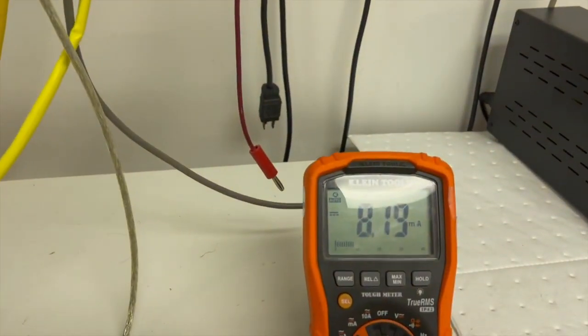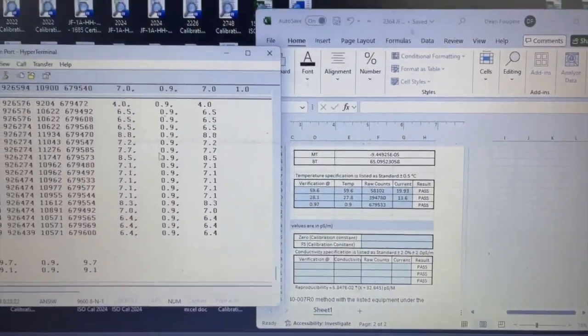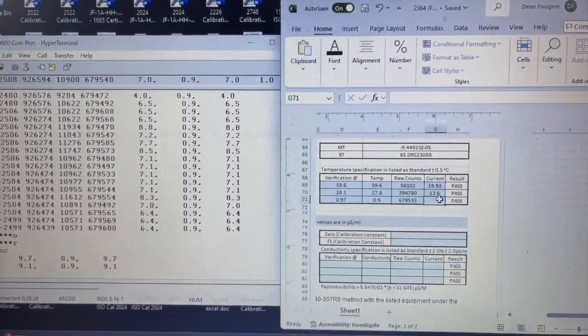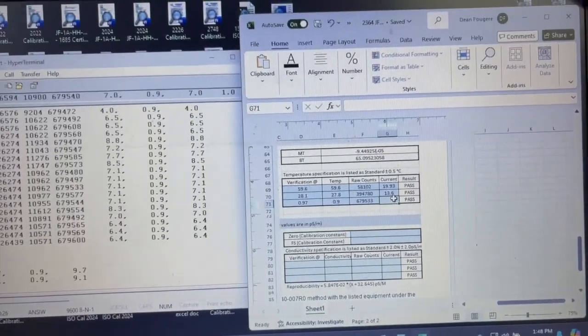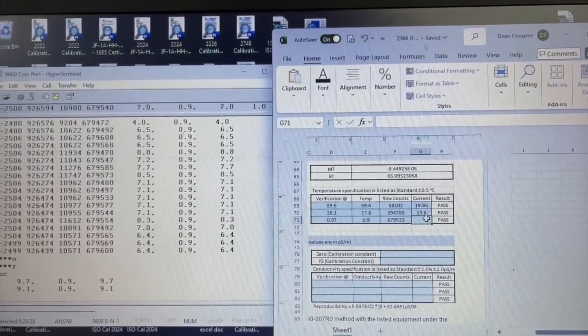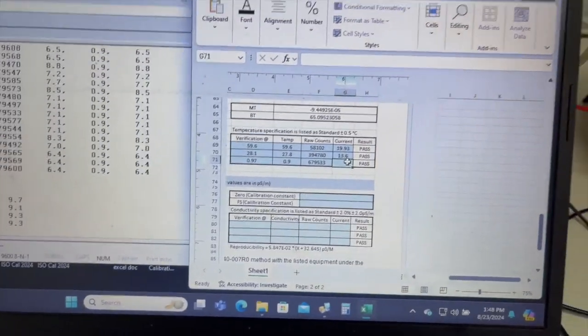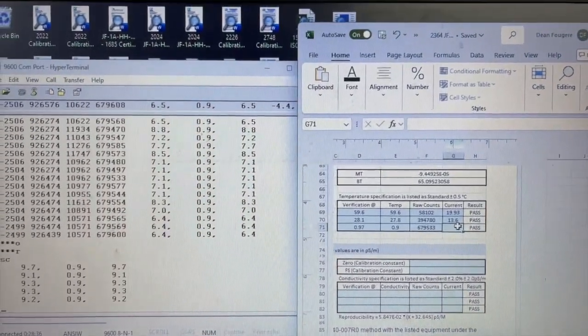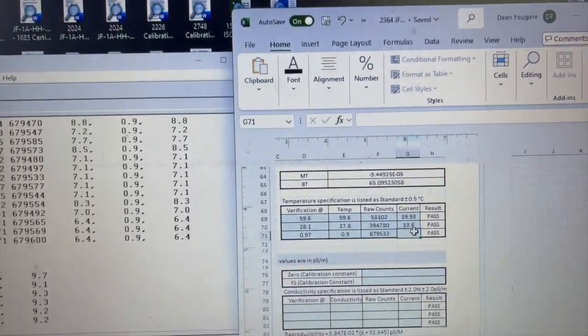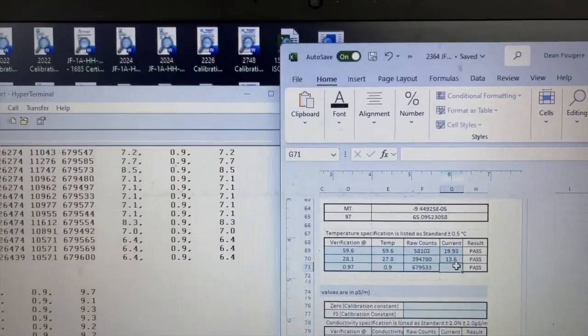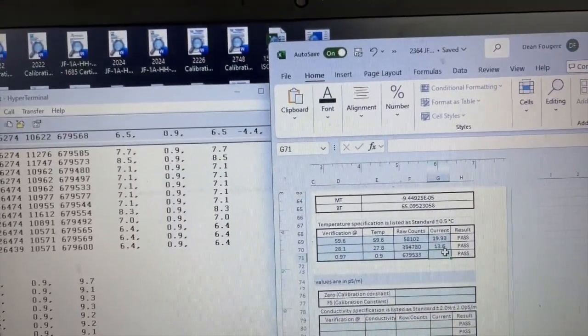0.9, and we have a voltage of 8.19, which is correct. We're not getting all the way down to the 0 for the instrument, which is minus 20, because the temperature bath doesn't go that low. So that's why it's not 4.0 mA, it's 8.19, because you're only at 1 instead of minus 20 Celsius. So that on the scale makes sense.